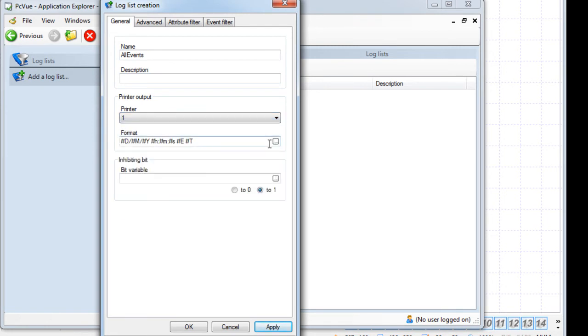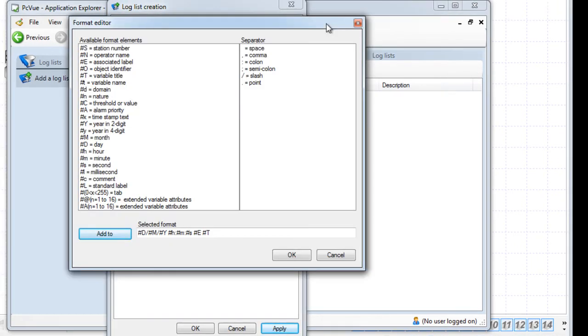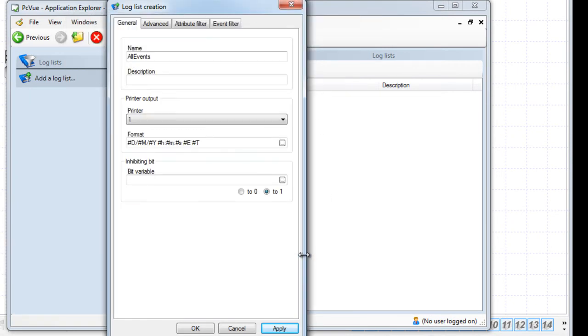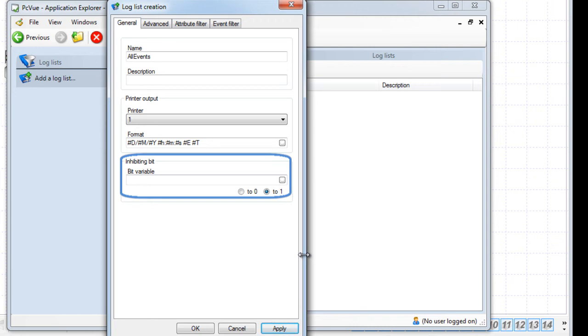Click on the ellipsis button to get more formats available. It is also possible to inhibit the record of events depending on the value of a specific bit. This could be very useful to avoid recording data while a process is in maintenance, for example.